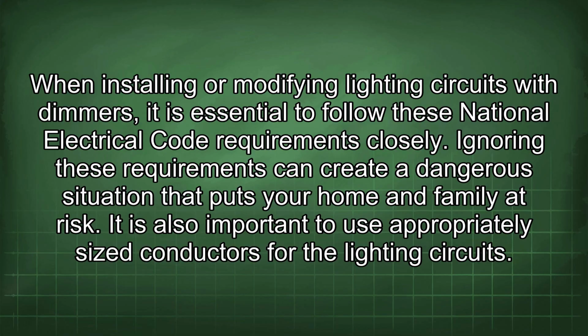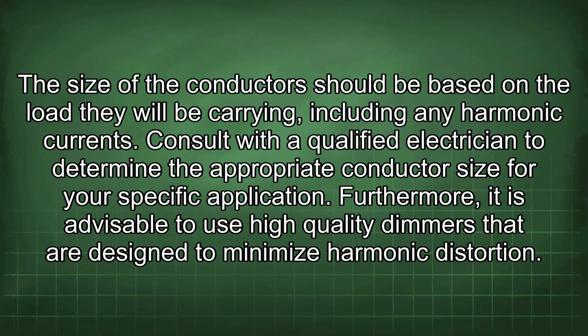It is also important to use appropriately sized conductors for the lighting circuits. The size of the conductors should be based on the load they will be carrying, including any harmonic currents. Consult with a qualified electrician to determine the appropriate conductor size for your specific application. Furthermore, it is advisable to use high-quality dimmers that are designed to minimize harmonic distortion.